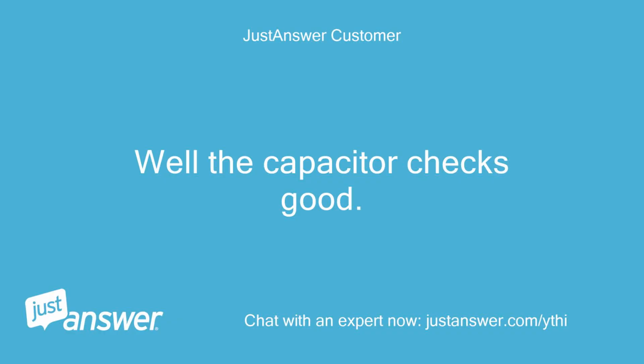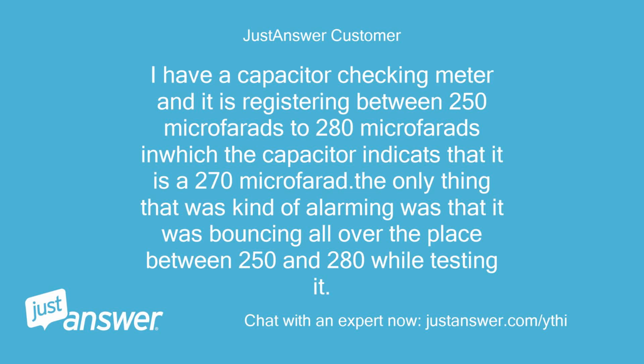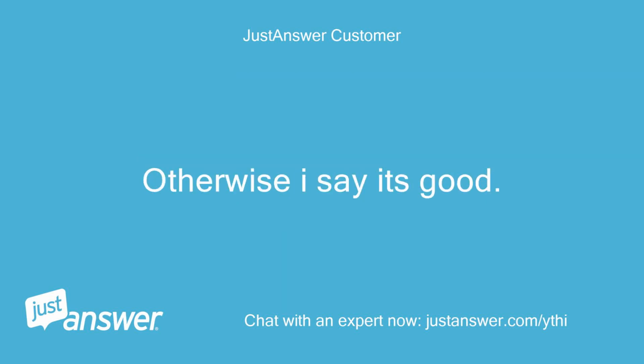Well, the capacitor checks good. I have a capacitor checking meter and it is registering between 250 microfarads and 280 microfarads, and the capacitor indicates that it is a 270 microfarad. The only thing that was kind of alarming was that it was bouncing all over the place between 250 and 280 while testing it. Otherwise, I'd say it's good.